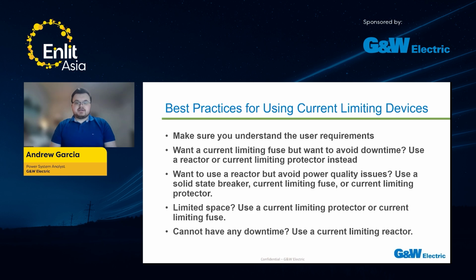You want to use a reactor, but you want to avoid any power quality issues that might result. You want to use a solid state breaker, current limiting fuse, or current limiting protector instead. Each of these devices would have low impedance and therefore have minimal effect on power quality in your system. There would be virtually no voltage drop. You have limited space. That's going to narrow your options a little. You want to use a current limiting protector or a current limiting fuse. Not have any downtime, use a current limiting reactor.